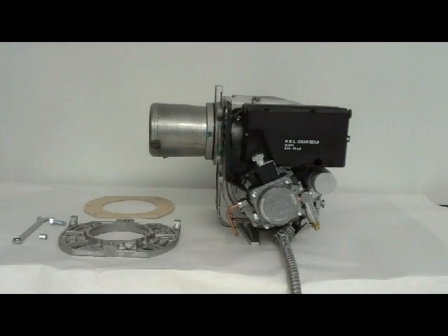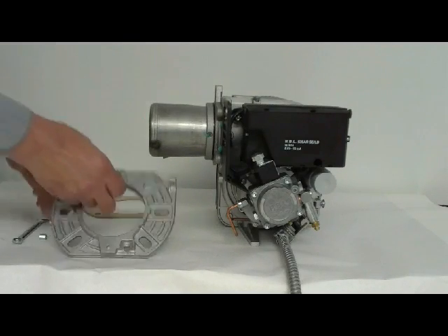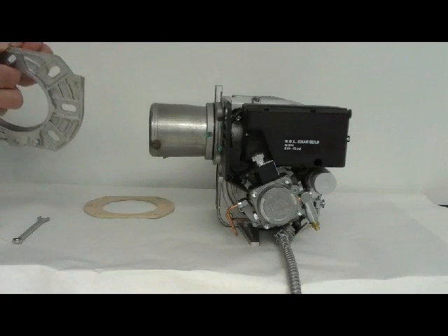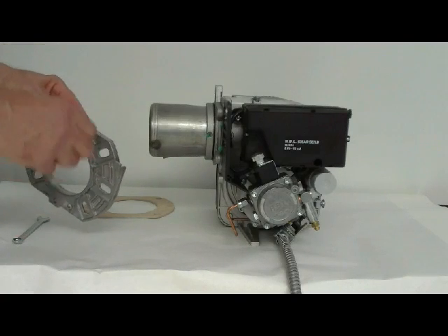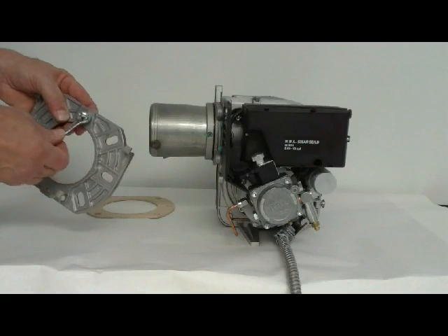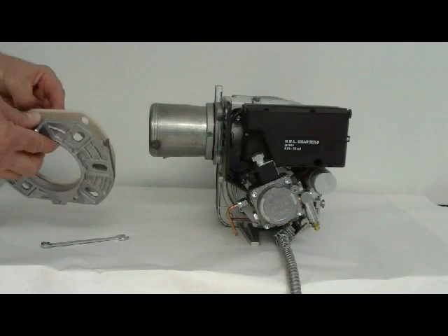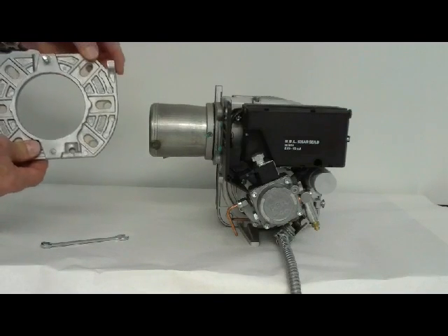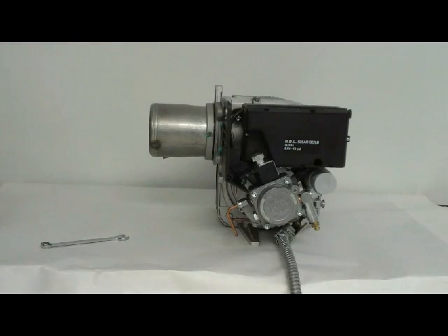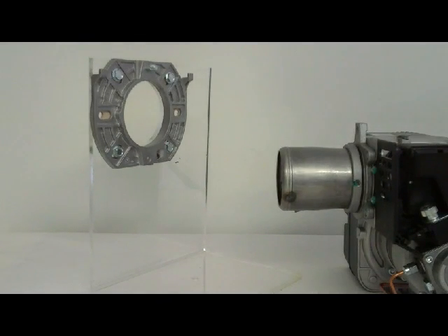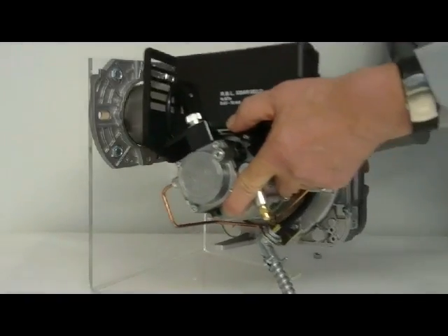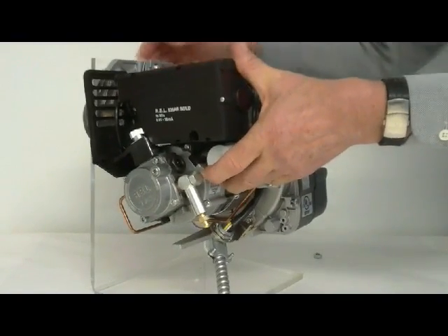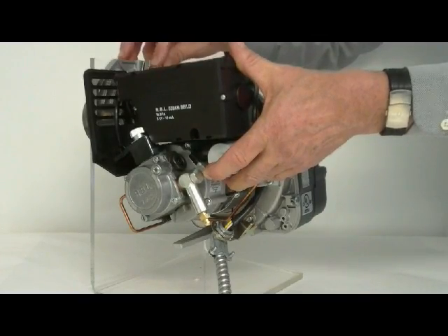To attach the burner to the boiler, first assemble the universal mounting flange by attaching the captive bolt and the retaining nut. Insert the provided gasket onto the universal flange and the universal flange is attached to the boiler. Burner is attached to the mounting flange and secured using the nut supplied in the accessory package.